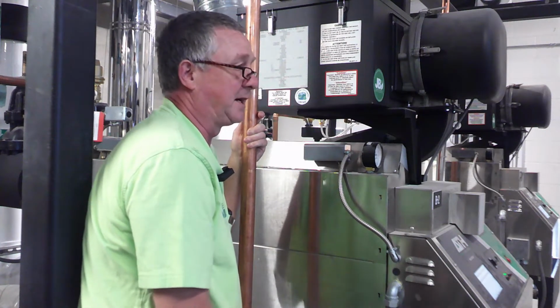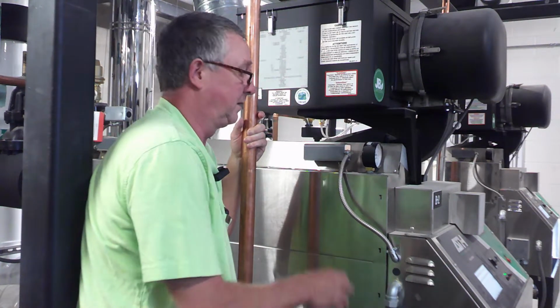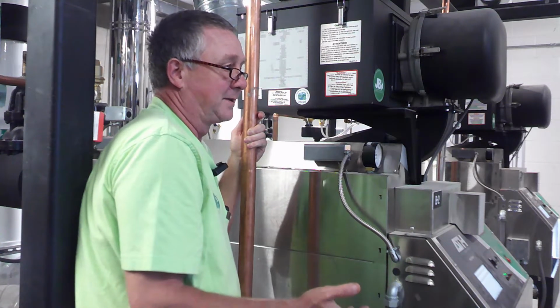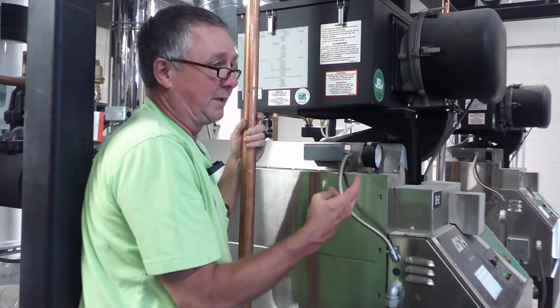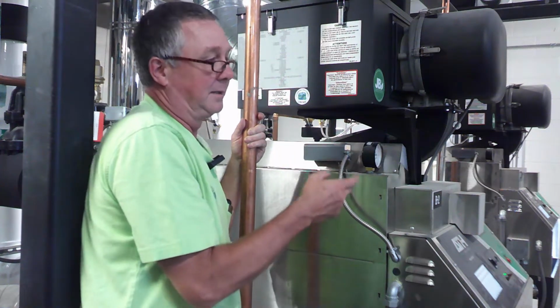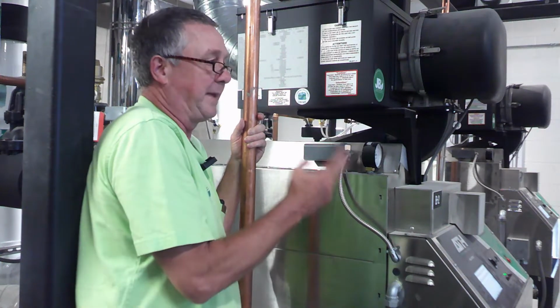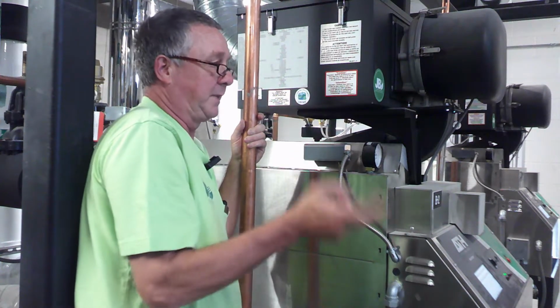The problem with that is a lot of stuff guys are trying to pass as a warranty. All this stuff has what's called a date code on it. You guys know what that is? So they stamp a date on there. It's usually 4 digits, like 20 of 22. That means it was made the 20th week of 22.